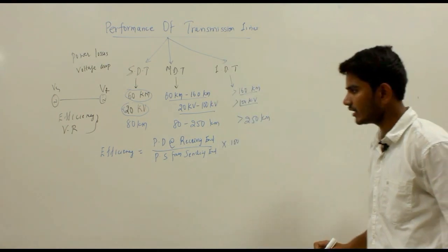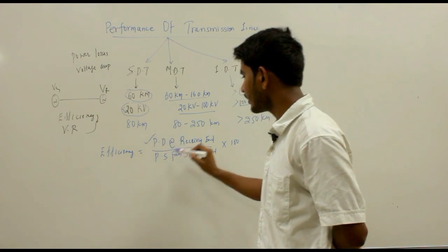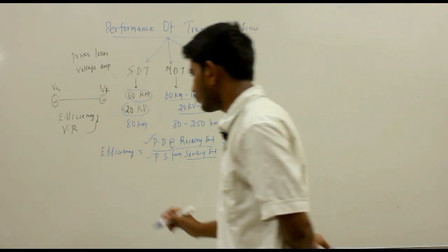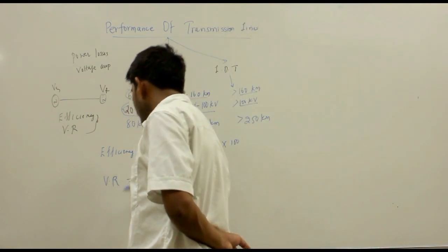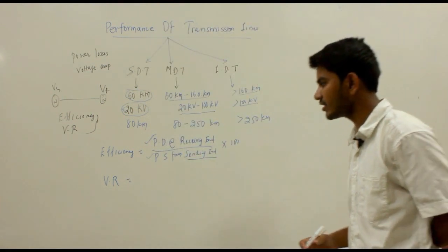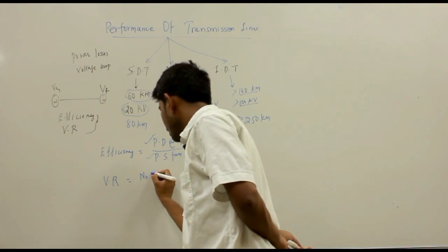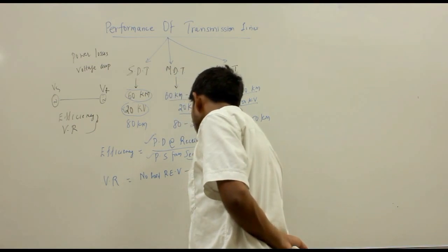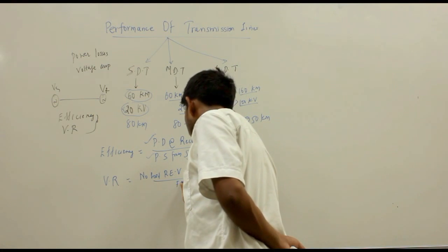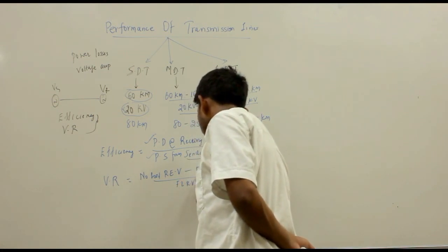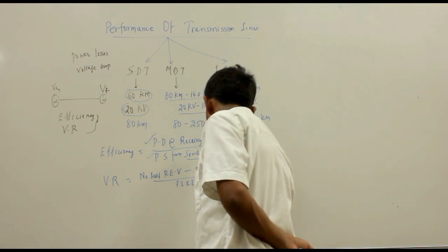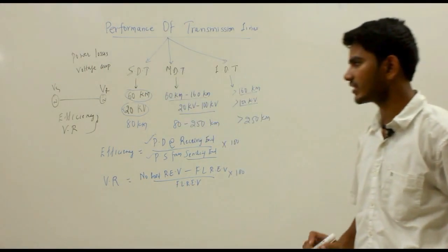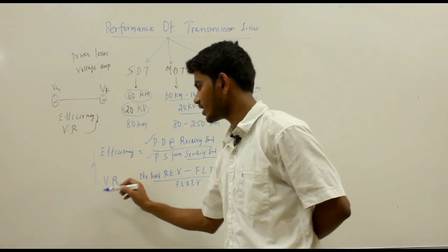The efficiency of any transmission line is the ratio of power delivered at the receiving end to the power sent from the sending end. The voltage regulation is a measure of change in the receiving end voltage from no load to full load condition — that is, no load receiving end voltage minus full load receiving end voltage, divided by full load receiving end voltage, multiplied by 100. The performance of any transmission line can be decided on these two factors: efficiency and voltage regulation.